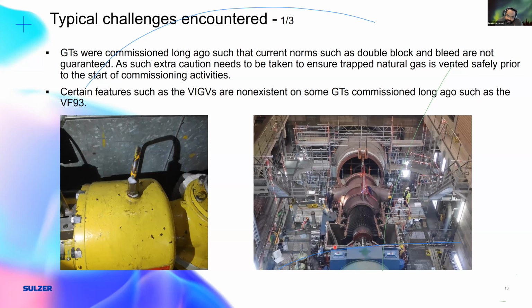This concrete building is actually the air intake housing. Air is sucked in through the concrete underneath into a manifold that allows it to go into the compressor. In this instance there was no IGV, so the work was simpler, but it also meant that when you had emission requirement issues, you had no possibility to introduce a degree of control.